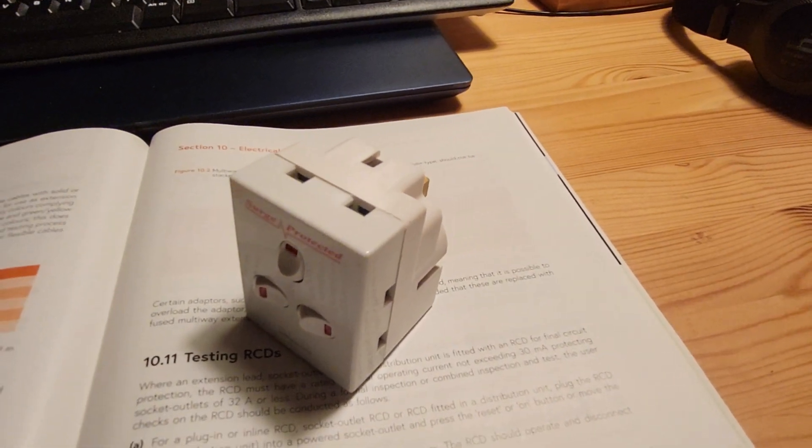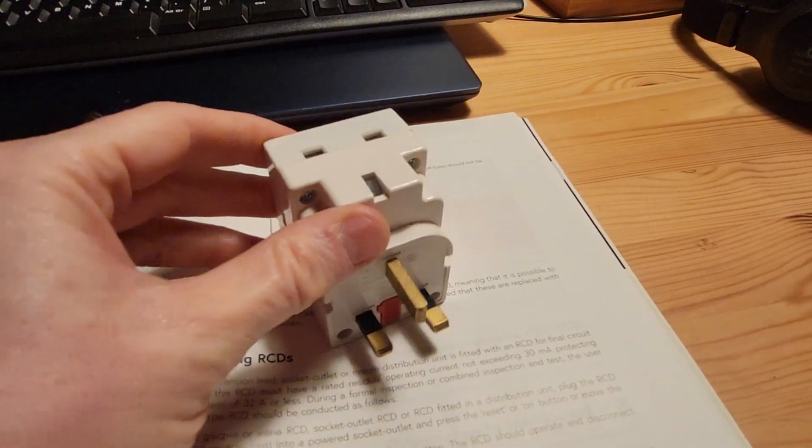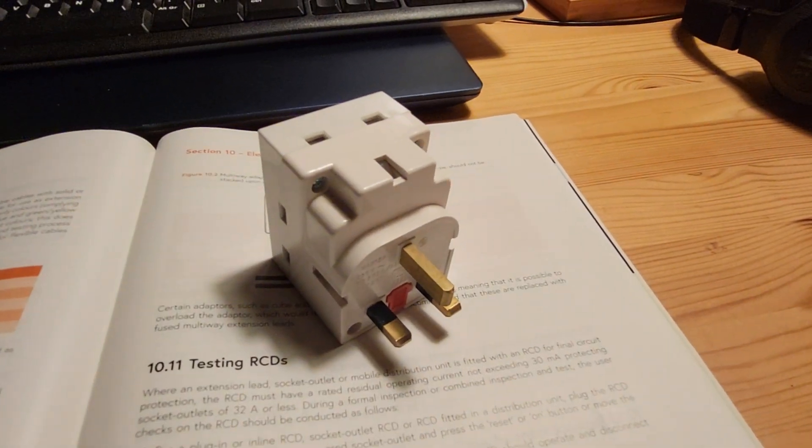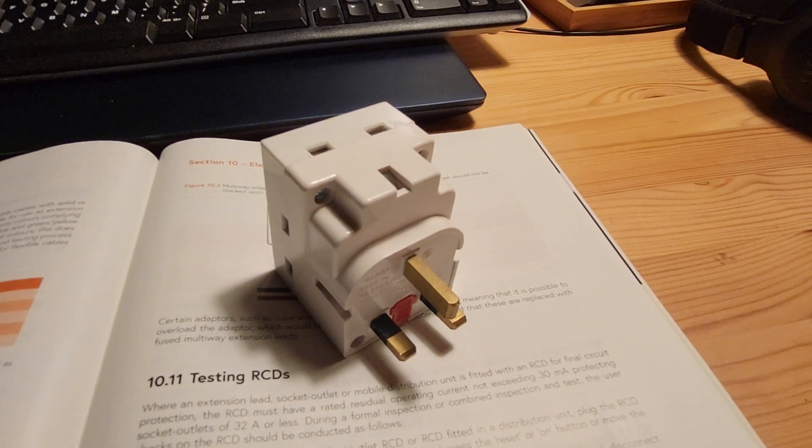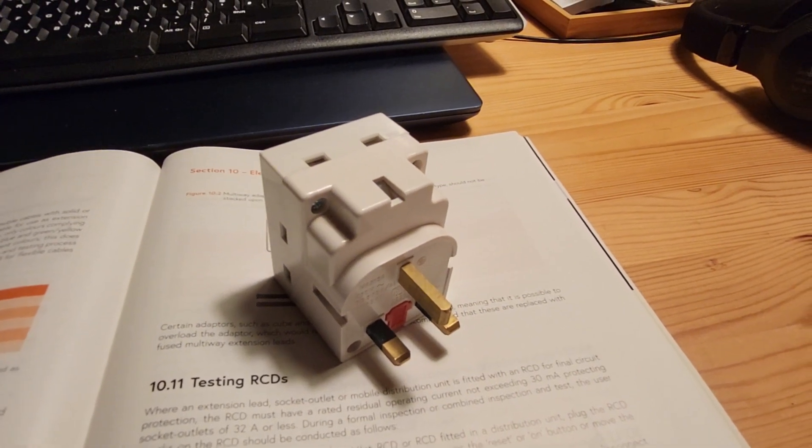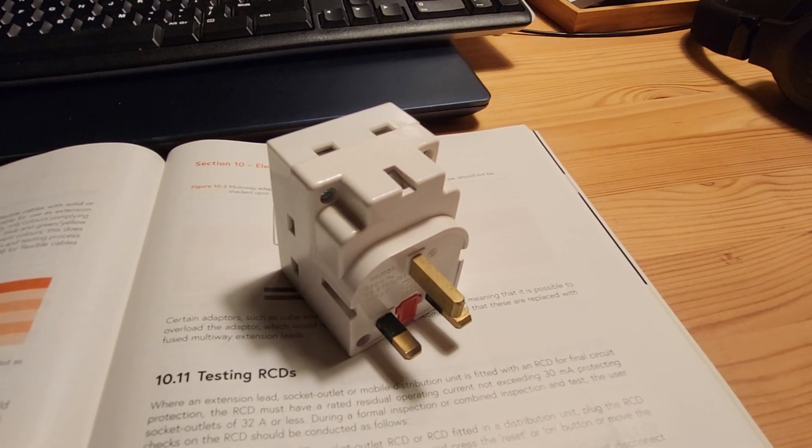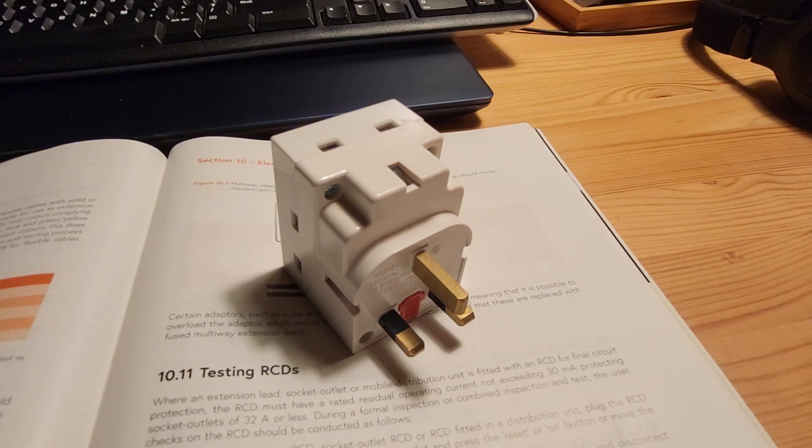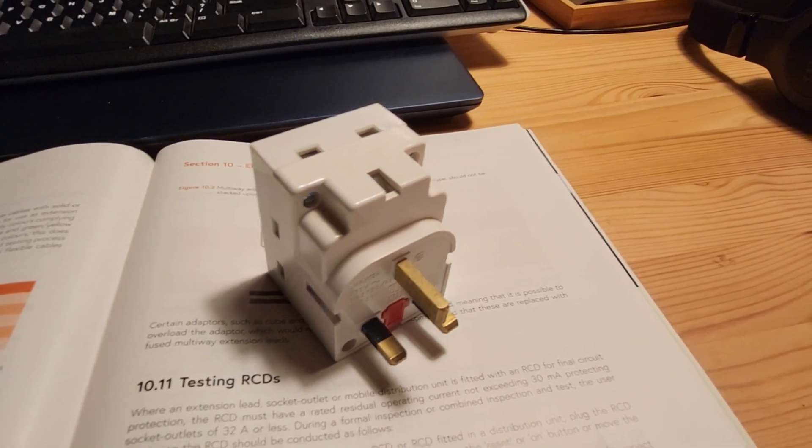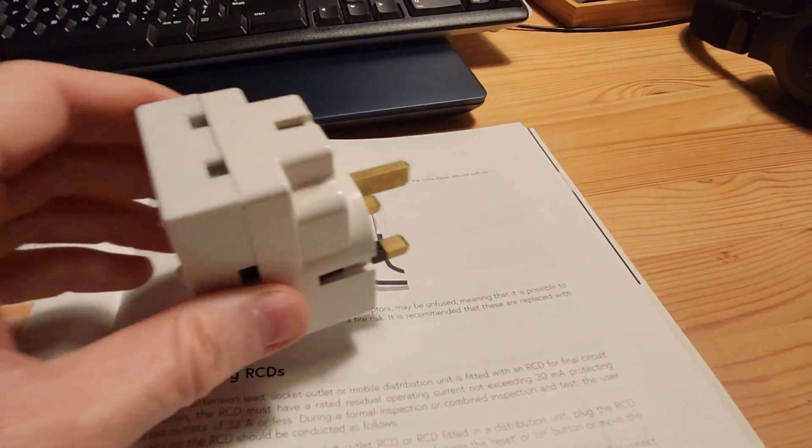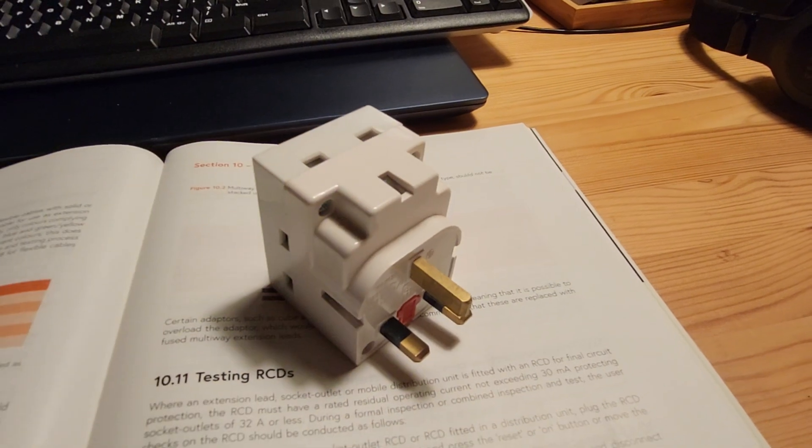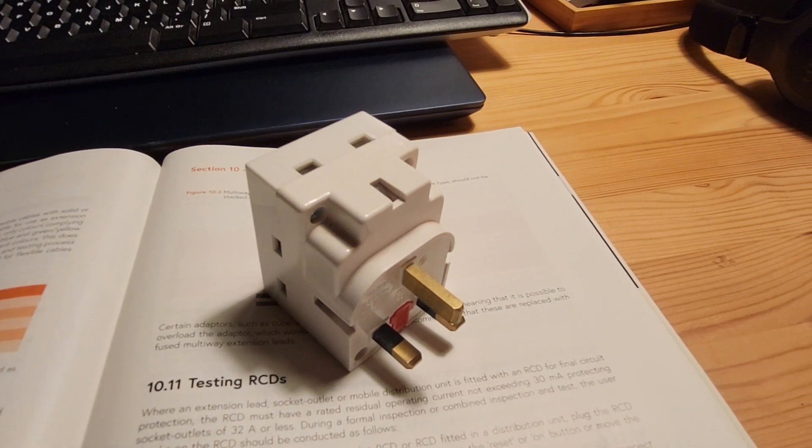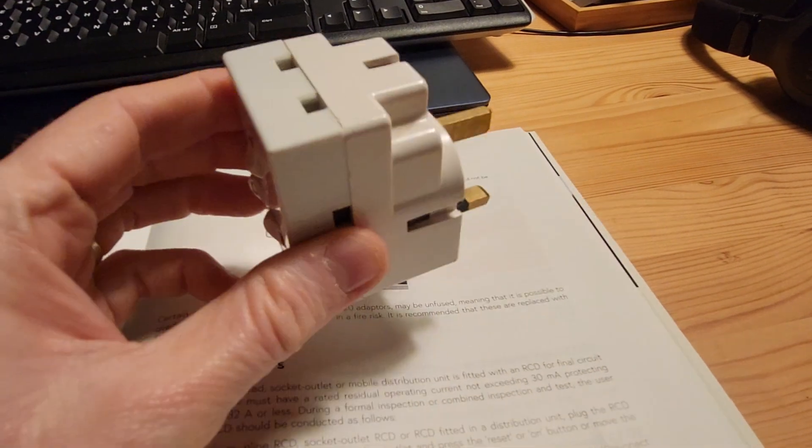So what would I do in this situation? Well, what I would do if I came across a two-way adapter, I would quite simply, I would record it on your test results as a failure. And then you'd put in your notes that the code of practice recommends that these are replaced. And then I would fail it.